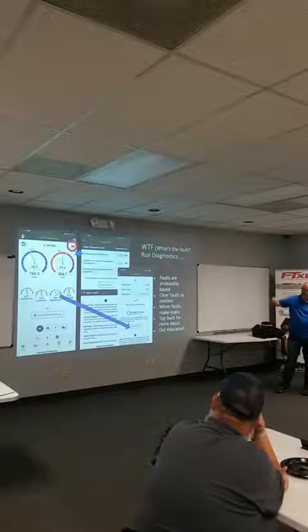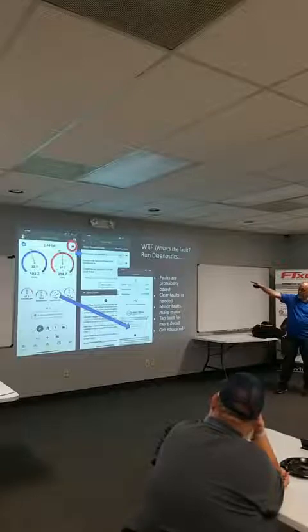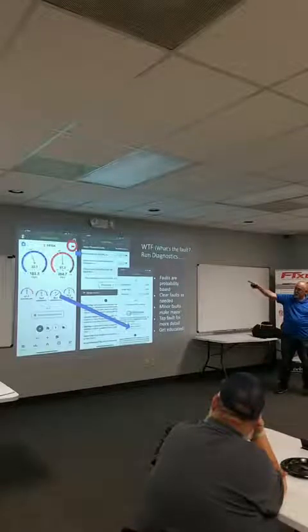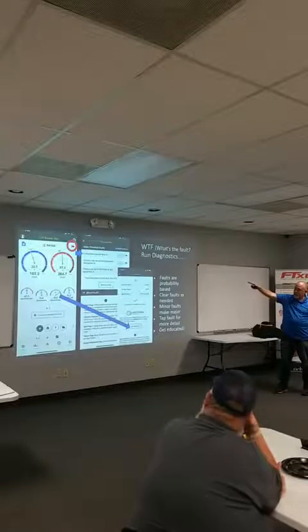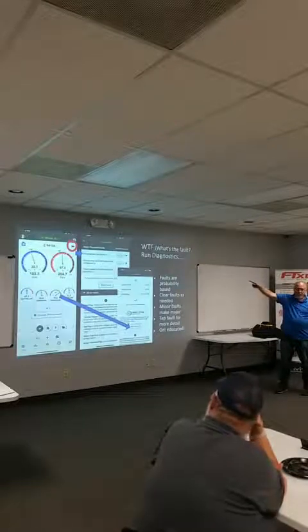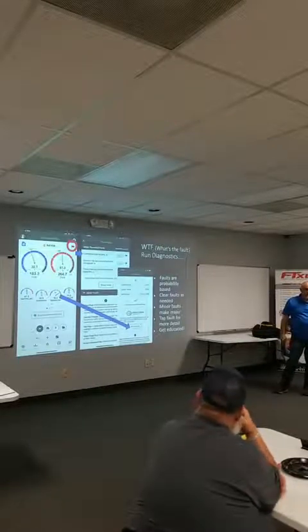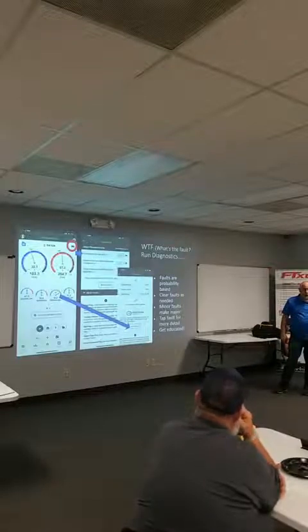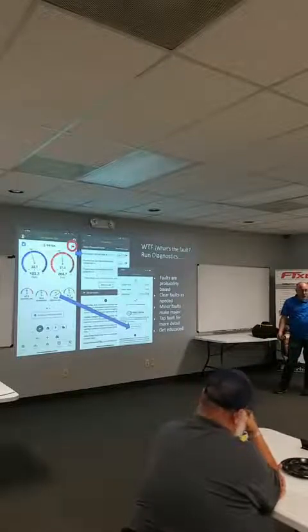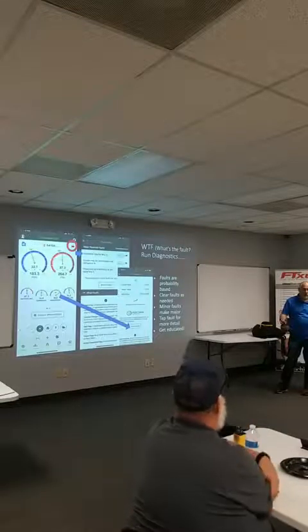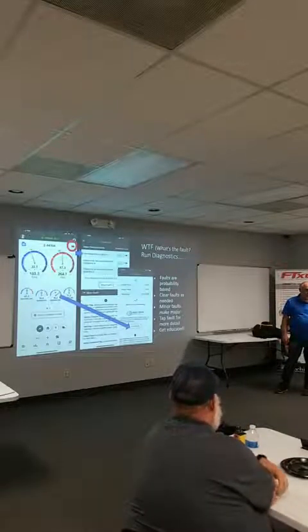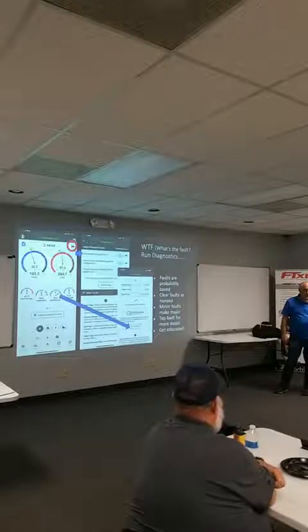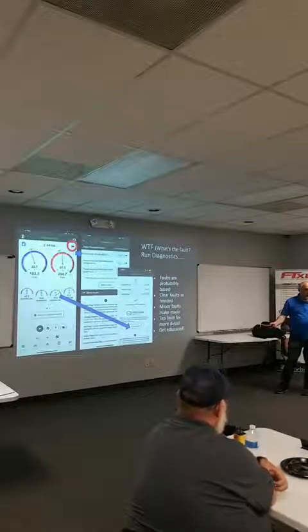I can't tell if your condenser's dirty or not through software, because you could also have an overcharged refrigerant. In fact, in this system, that little 2 next to the flag means there's 2 symptoms of an overcharge, right? So I could have high head pressure and I could have high subcooling. You go, well, how the hell does high head pressure cause high subcooling? Well, if you have a low ambient temperature and a big condenser coil, what is the coldest the liquid line temperature can get to? What's cooling down a condenser? Outdoor air, right? So the coldest the liquid can get is the outdoor air temperature.